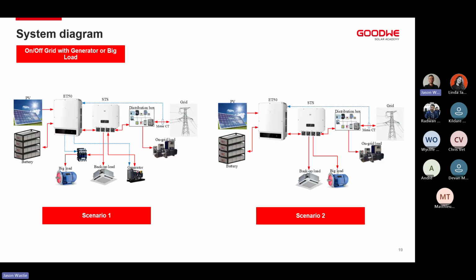With regards to the generator port on the STS, we have two different ways we can use it. On the inverter itself, we have two 5-amp dry contact relays. We use those two dry contact relays for two things: one is for your generator's auto start-stop functionality, and two is for smart load control, or a secondary AC output load control, big load mode, however you want to word it. It is essentially allowing us to have two different backup outputs and to control one of them.